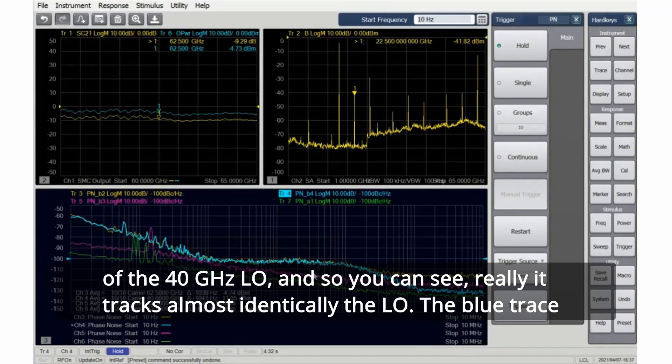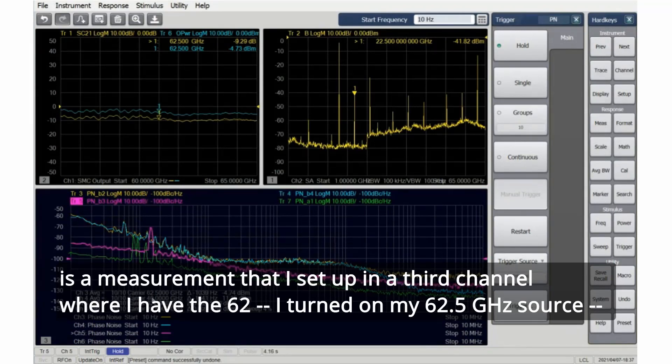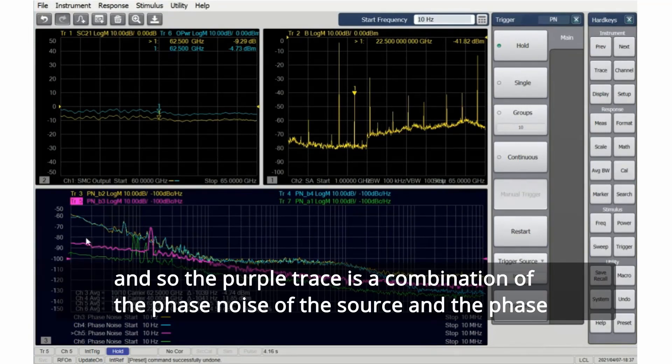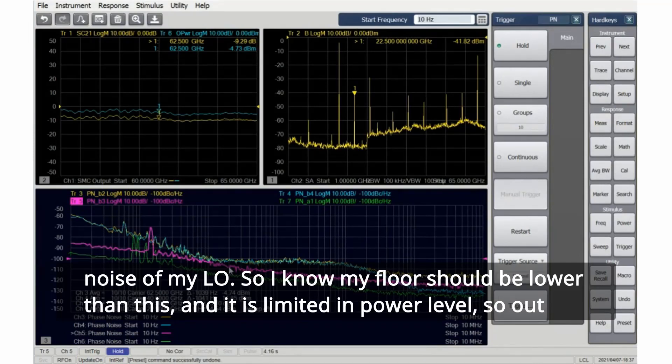The blue trace is a measurement that I set up in a third channel where I turned on my 62.5 gigahertz source. The purple trace is a combination of the phase noise of the source and the phase noise of my LO, so I know my floor should be lower than this and it is limited in power level.